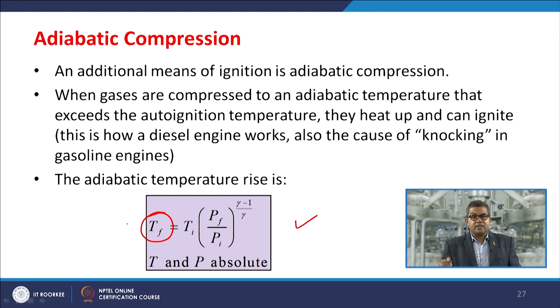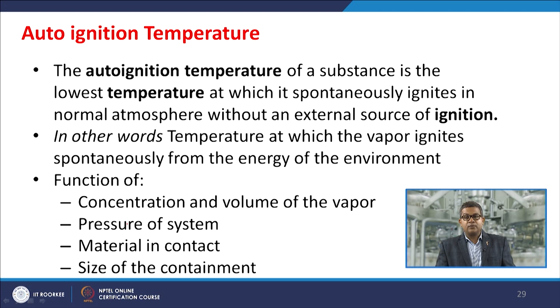Now, because we have discussed auto ignition temperature in adiabatic compression, it is our prime duty to have a look at what auto ignition temperature is. The auto ignition temperature of a substance is the lowest temperature at which it spontaneously ignites in a normal atmosphere without an external source of ignition. In other words, it is the temperature at which the vapor ignites spontaneously from the energy of the environment. If you compare with adiabatic compression, the temperature there is on the higher side than the auto ignition temperature, and if sufficient quantity of oxygen is available, then definitely it will ignite. Now, this AIT is a function of concentration and volume of the vapor, the pressure of the system, the material in contact and the size of containment.